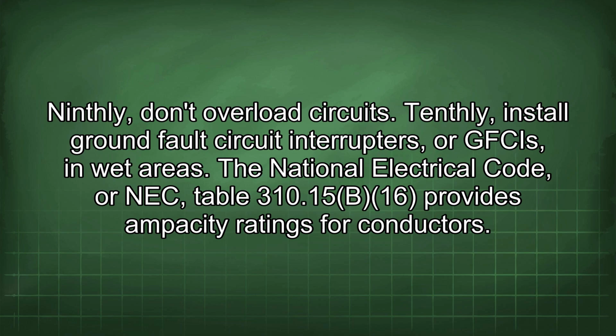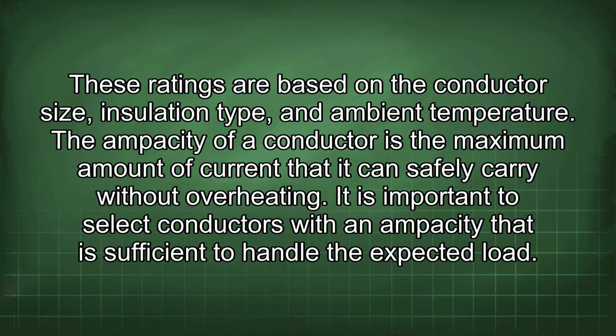The National Electrical Code, or NEC, Table 310.15(B)(16) provides ampacity ratings for conductors. These ratings are based on the conductor size, insulation type, and ambient temperature. The ampacity of a conductor is the maximum amount of current that it can safely carry without overheating. It is important to select conductors with an ampacity that is sufficient to handle the expected load.